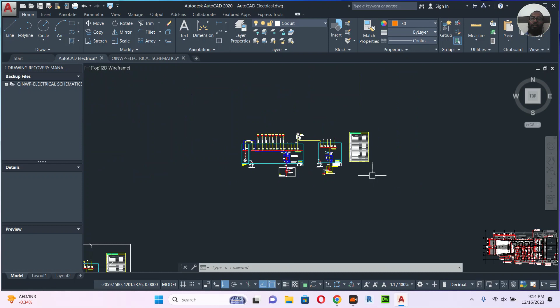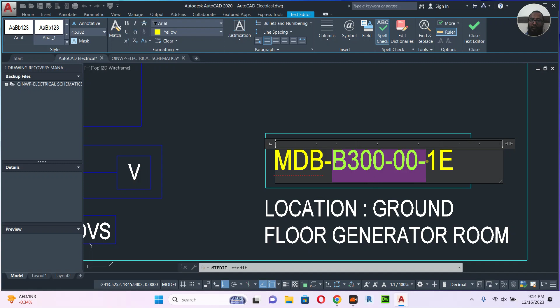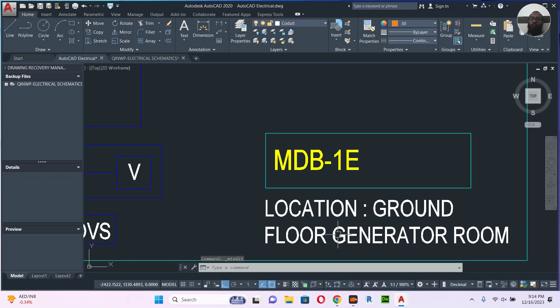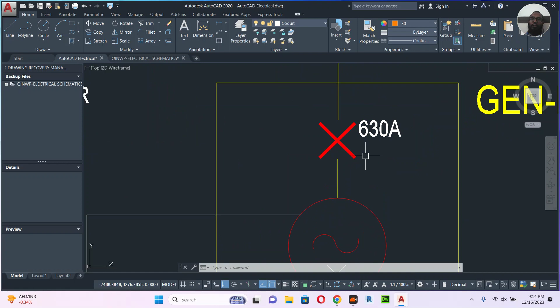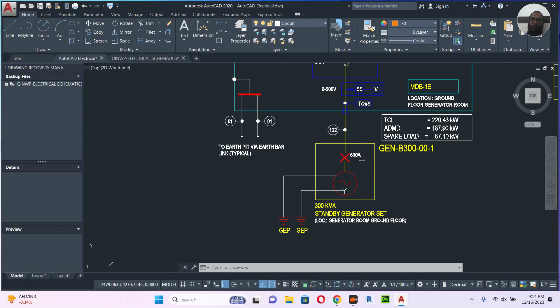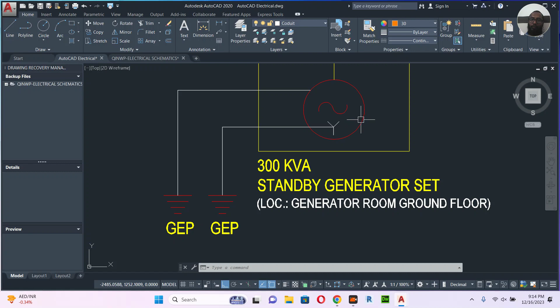So how will this one come? The generator will go to the panel. Which panel? This is MDB, let's consider 1E, the ground floor generator room, MDB 1E. For this generator, you will have a 630 ampere breaker from the generator to the MDB. How much power does this generator provide? It generates 300 kVA. If you multiply 300 kVA by the power factor, maybe 0.9 or 0.8, you will get kW.